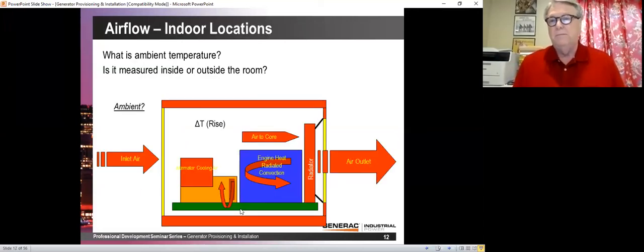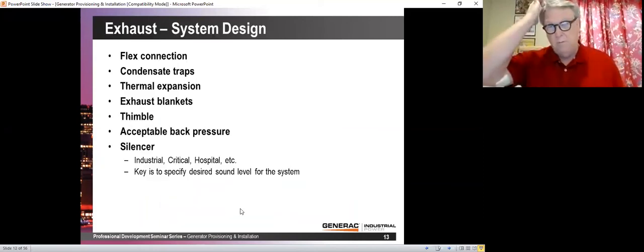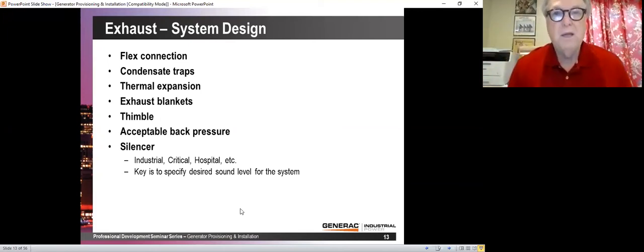There's your little diagram of air coming in, air going out, and of course the ambient air temperature makes a great deal of difference also. Exhaust, you need a flex connection. You need condensate traps. We talked about that, the little tube that allows you to drain and allows the water to go into the condensate trap and not back into the engine. Allow for thermal expansion, have exhaust blankets, a thimble, have acceptable back pressure, and the silencer can be either a residential silencer or industrial or critical or hospital grade.